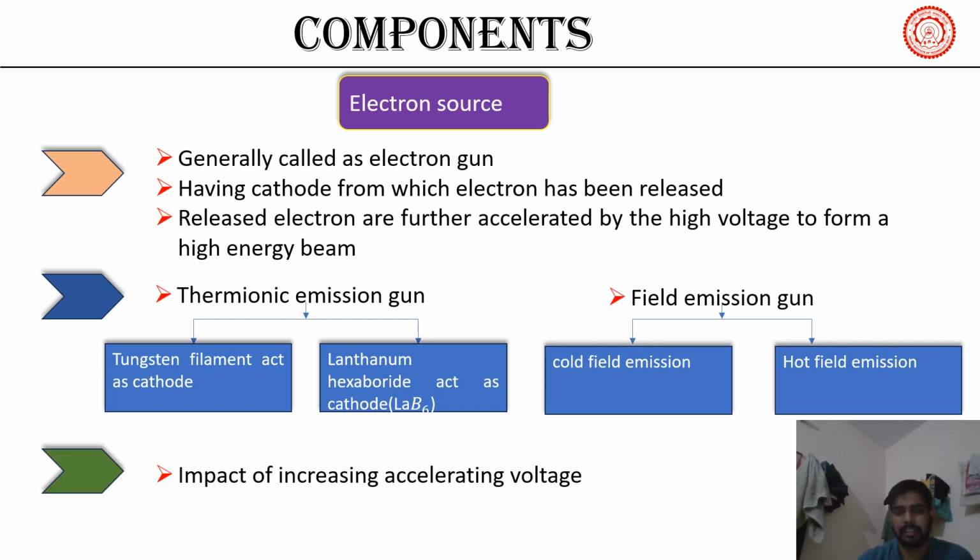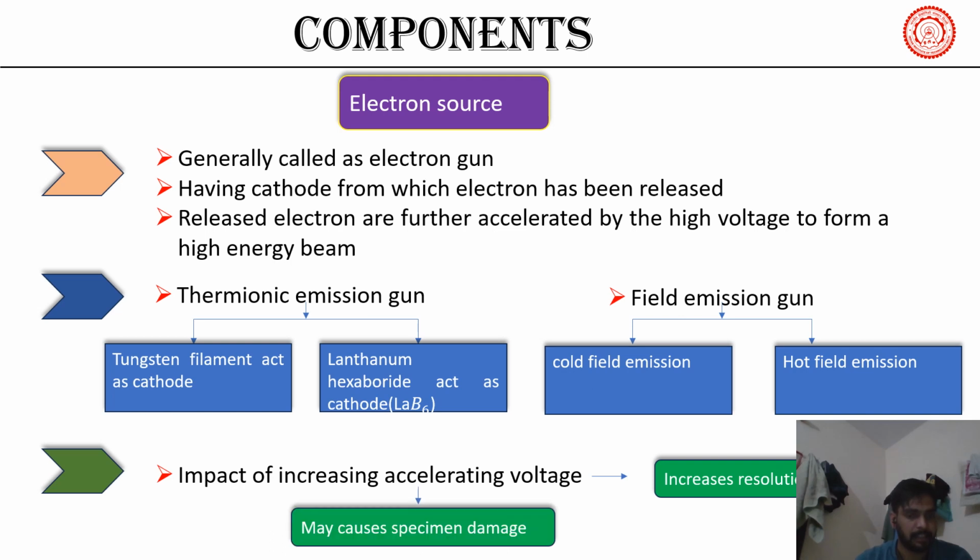Now, is there an impact of increasing the accelerating voltage? Two impacts have been seen. The first is that if we increase the accelerating voltage, then we increase the resolution. And the second is that if we increase the accelerating voltage, then it may cause specimen damage.